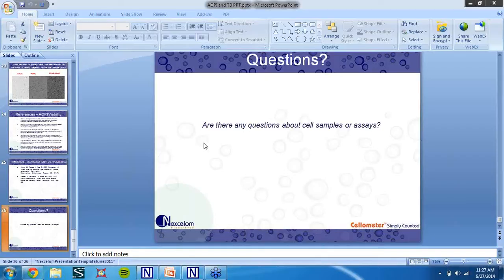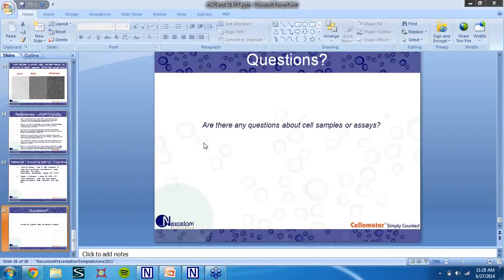Another question: does cell size have anything to do with Trypan Blue versus AOPI? If you're working with a cell line and want to analyze cell sizes, the cell size measurement is best done in brightfield — you may be looking at two different populations. If you do not have a clean cell sample and want to look at cell size, you can use the fluorescent method, but it's important to set up your exposure times properly. If cells are overexposed or too bright, the cell size measurement will shift to appear larger. Our assay setups in the software are optimized for most cell lines, but for clean samples, the best way is via brightfield.